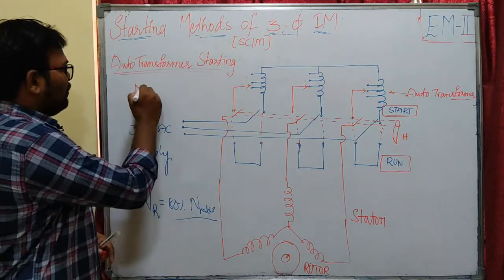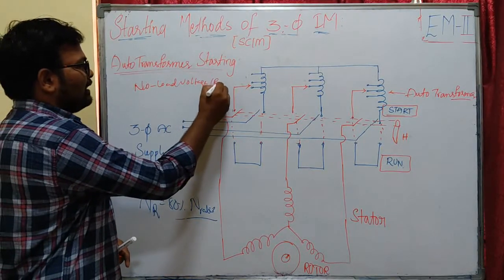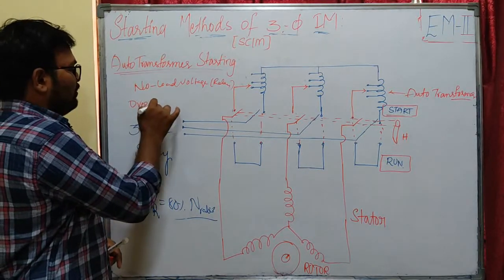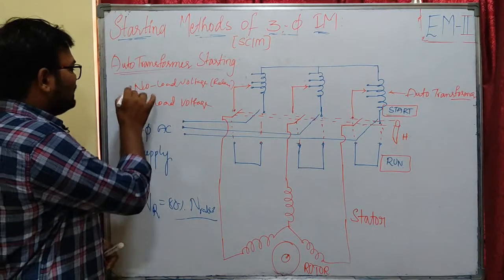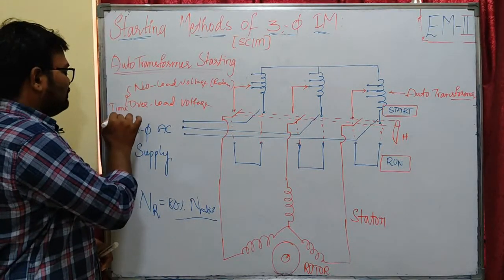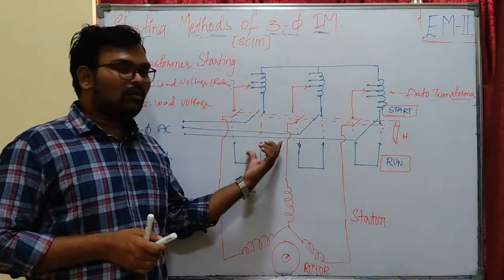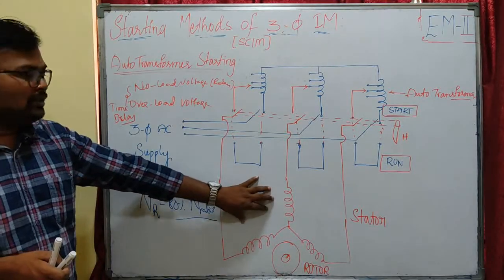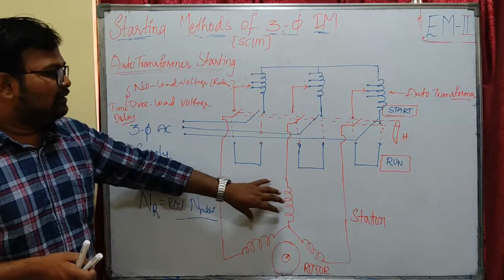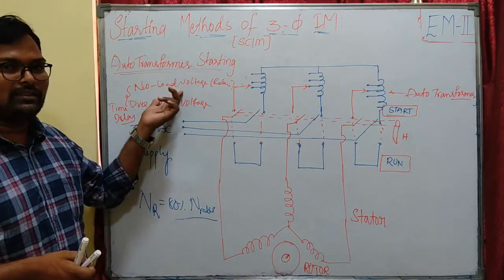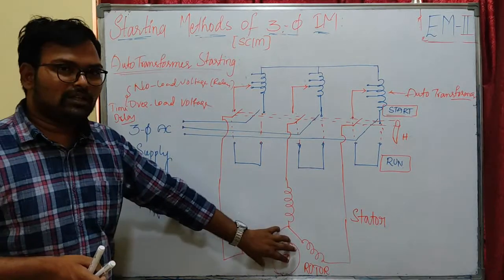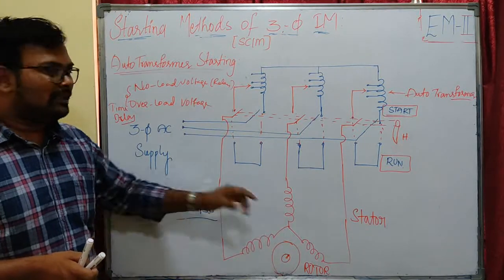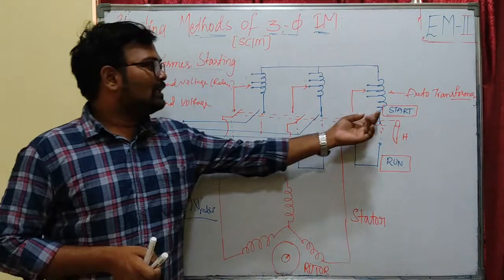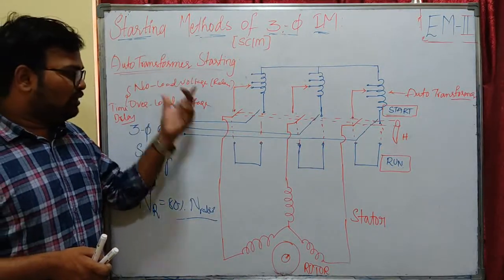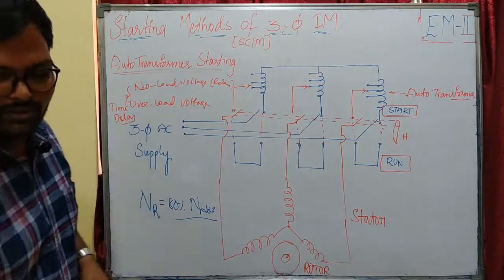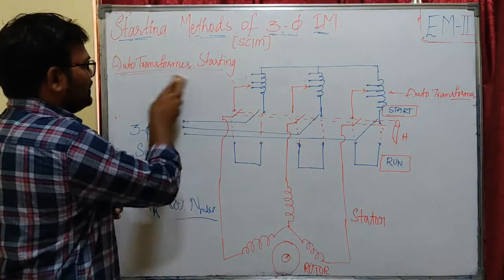So here we will be having a no voltage coil, that is a relay, and a full load or overload voltage relay. These are relays which are given with some time delay. At the time of switching, we may get no voltage for a short period of time to our induction machine. For that we use the no voltage relay, and it will hold the circuit for a short period of time without any voltage. And we have another, the overload relay: whenever the load on the motor is high, the overload relay will protect the overall circuit. These two are given some time delay, because at the time of switching from starting to running we will have no voltage on the stator for a moment, or at the time of overload we will have overload on the machine. These two relays I am not showing in the circuit, they are internally connected.